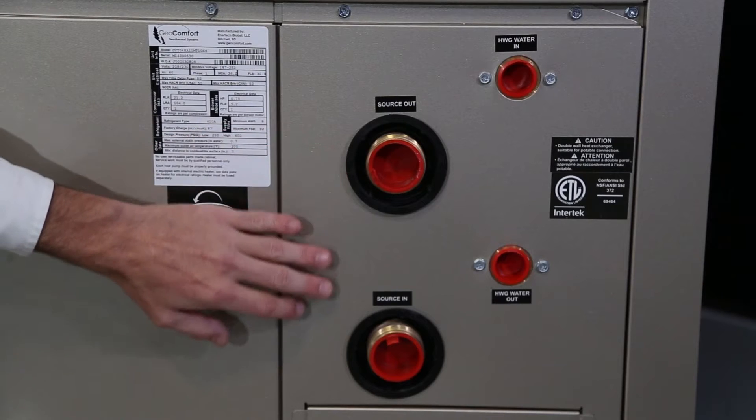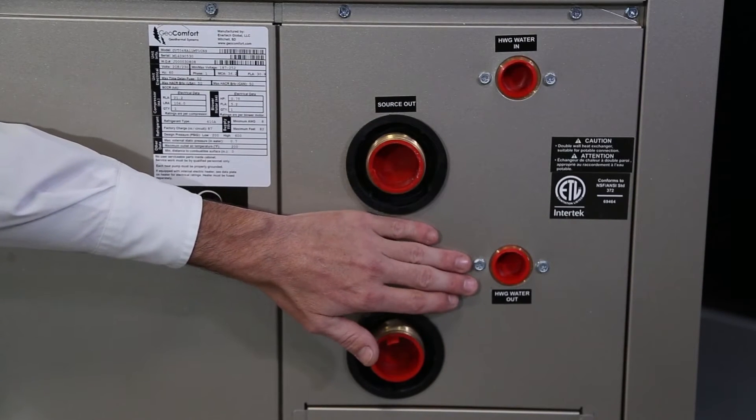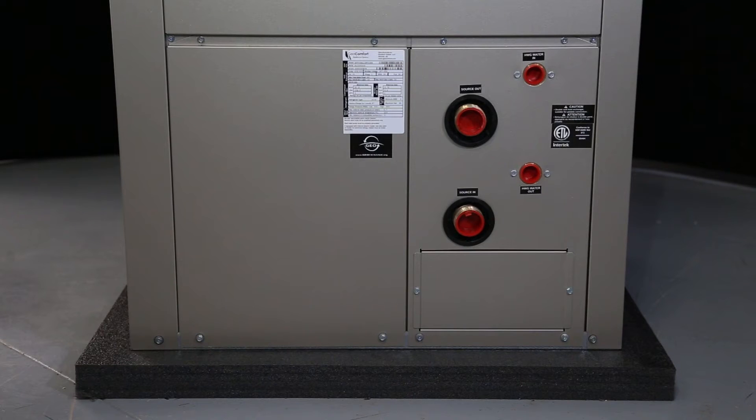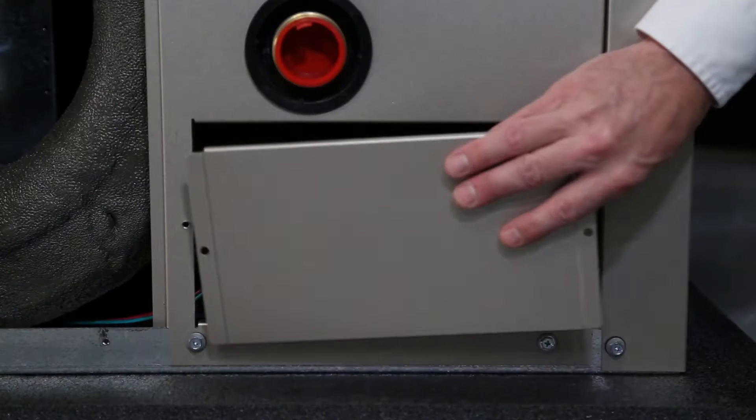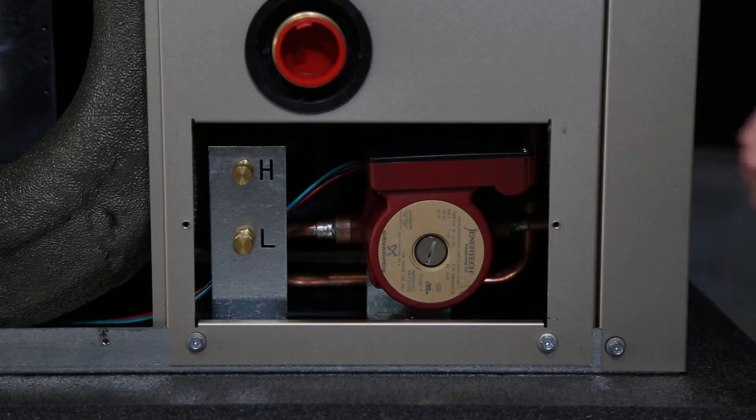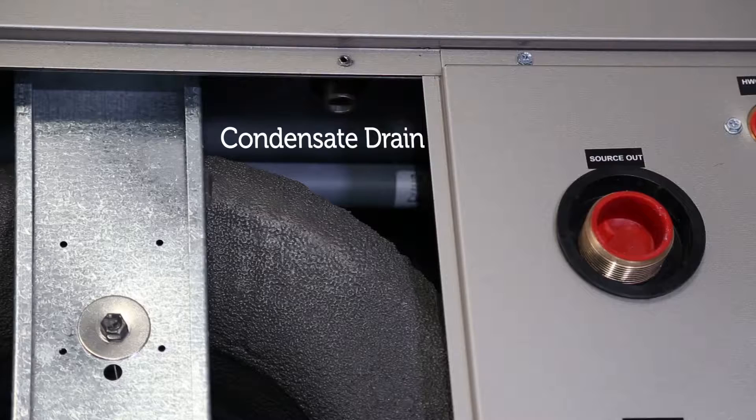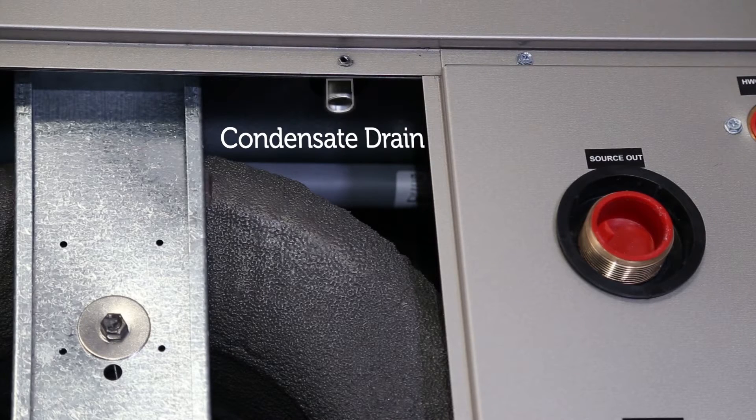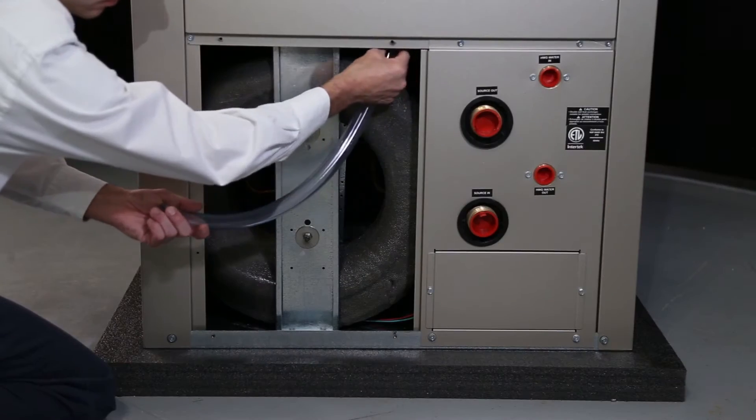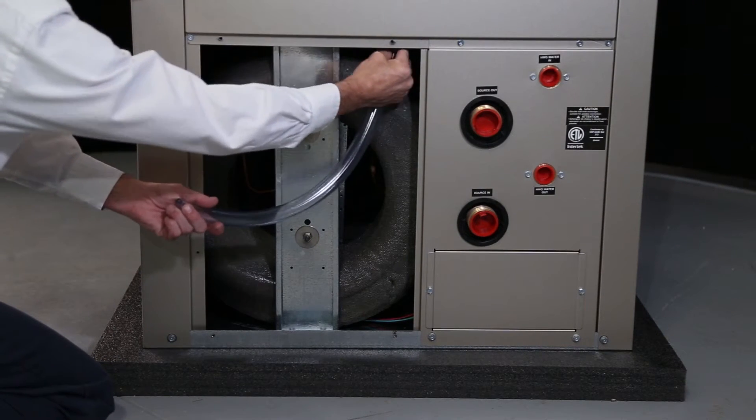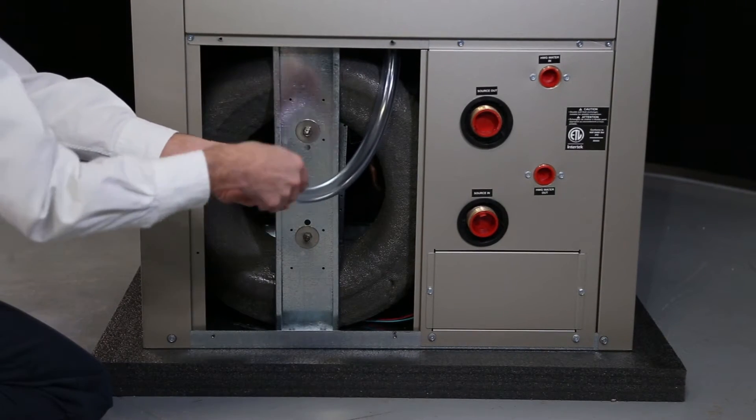The source in and out connections along with the hot water generator fittings are on the bottom of the air coil side of the unit. Under the water connections is the desuperheater pump and refrigerant ports. The condensate drain is in the center of the pan and is field selectable to exit on the coil side post in front or back. The drain options are labeled on the post.